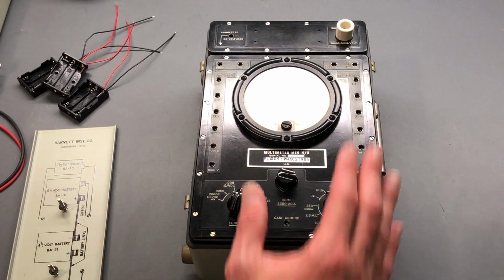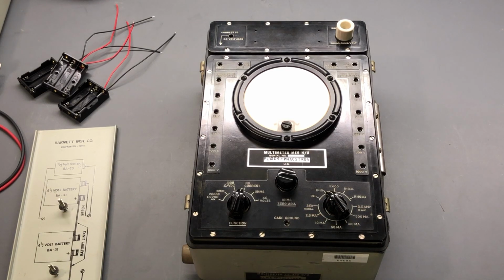So down here where we have the R times 1, test lead shorted, 60 milliamp draw. On the times 10 range over here, when you short the test leads, you'd have a 6 milliamp draw. The times 100 range is 600 microamps, and the times 1000 range is 60 microamps. Very, very small amount of current that actually flows. And again, that's only when the test leads are shorted.